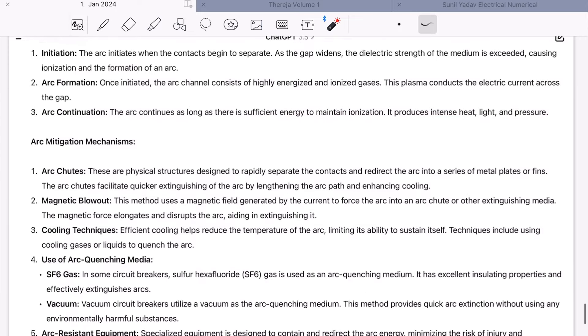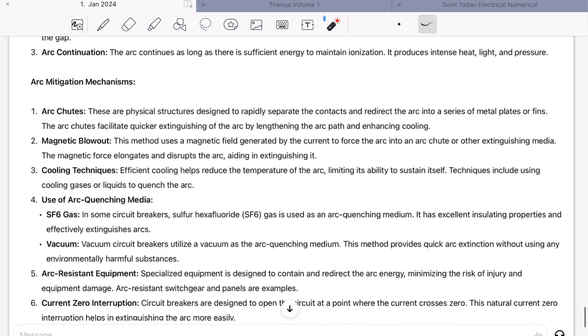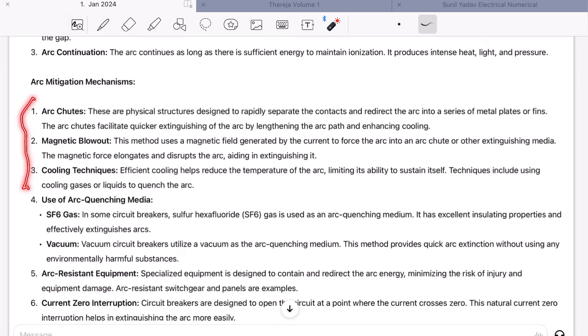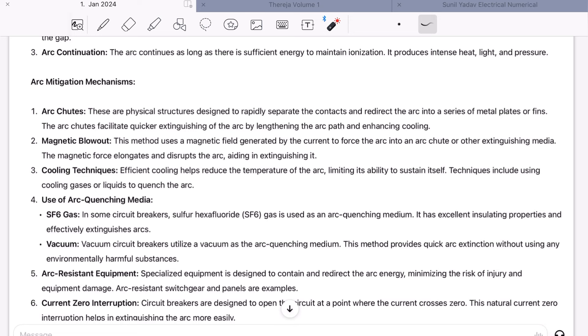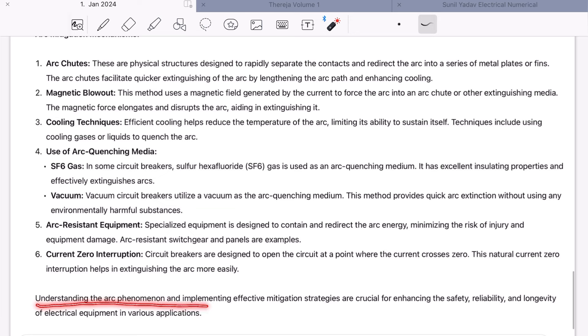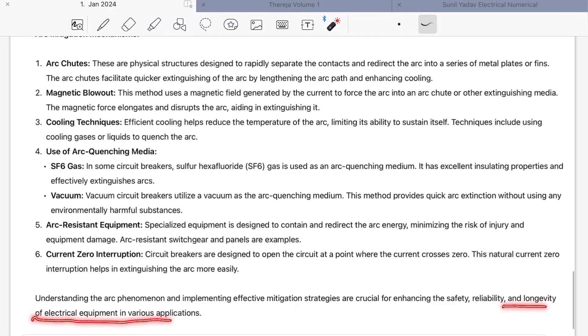Now how is the arc mitigated? There are various methods: arc chutes, magnetic blowout, cooling techniques, use of arc quenching media such as SF6, vacuum, or forced air, arc-resistant equipment, and current zero interruption. This is where different types of circuit breakers come from — the medium of arc quenching defines the type. If SF6 chemical is used, it is an SF6 circuit breaker; if vacuum is used, it is a vacuum circuit breaker; if air is used, it is an air circuit breaker. Understanding arc phenomena and implementing effective mitigation strategies are crucial for enhancing safety, reliability, and longevity of electrical equipment.